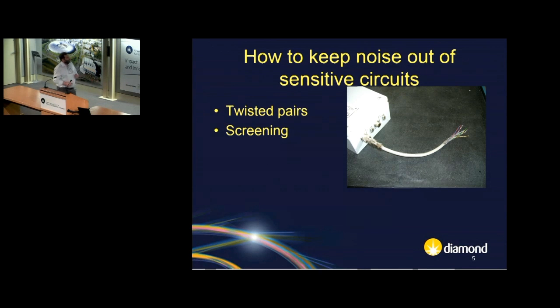One method is to put the signals through twisted pairs - those wires there are actually twisted pairs, so we use a lot of them. You'll also see there's a braid screen around that, copper braid, which is the screening element. It's connected to the metal shell of the connector and the metal of the box, so the box, the cable, and the connector form a continuous screen.